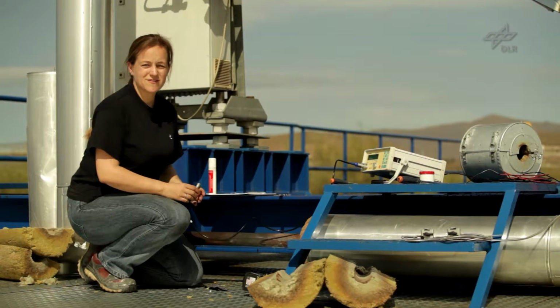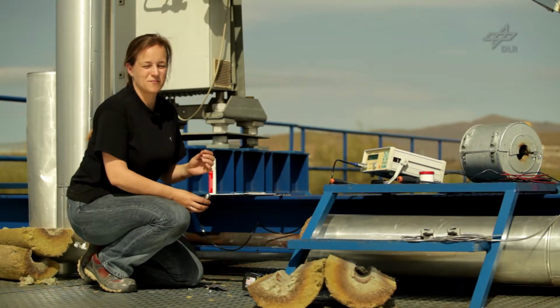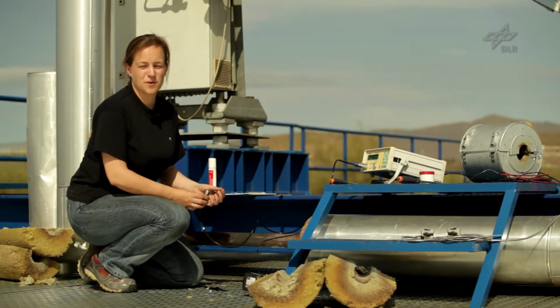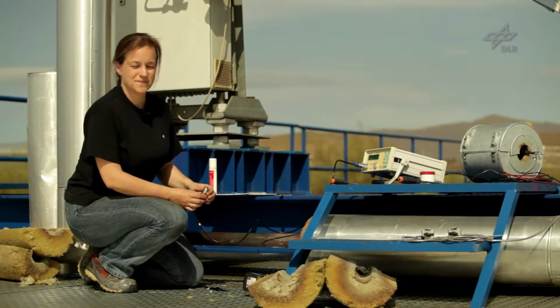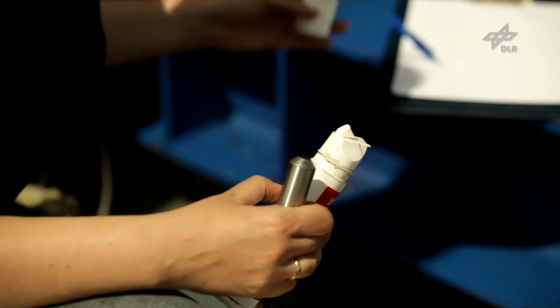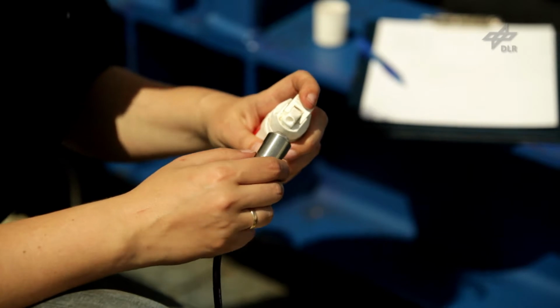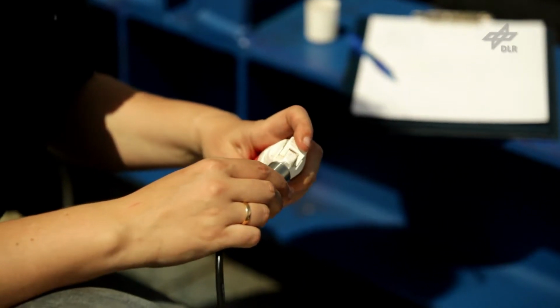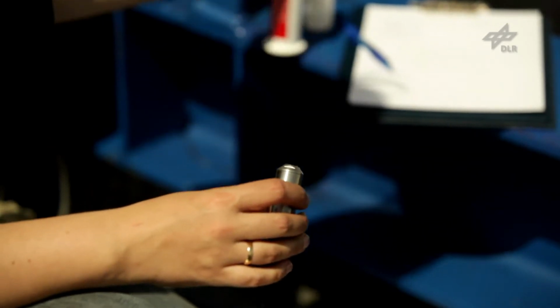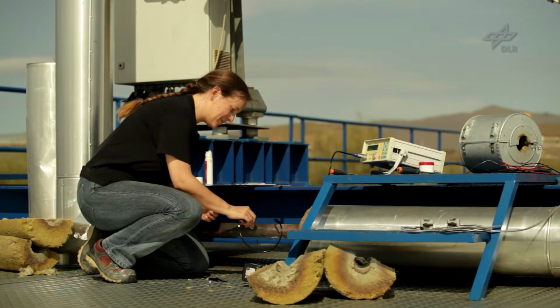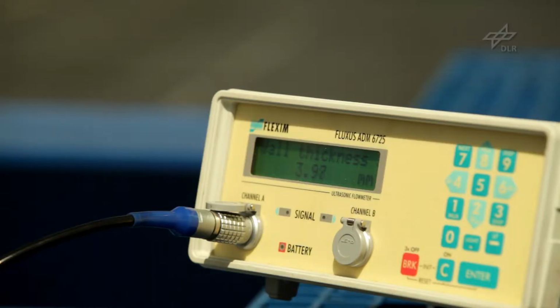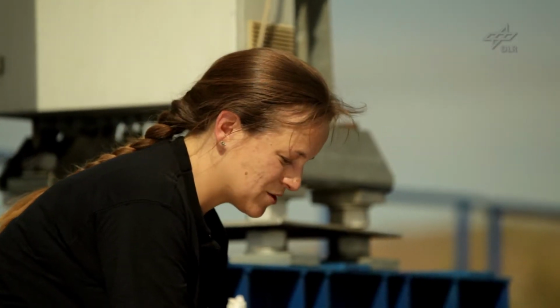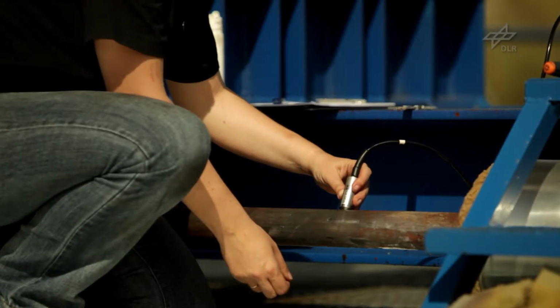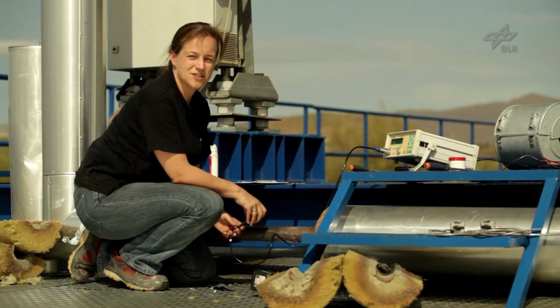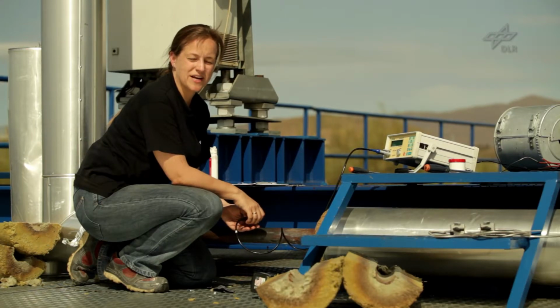The wall thickness of the pipe is determined by ultrasonic measurements. They use the travel time difference to determine the thickness from the time needed for the signal to pass through the wall material and its longitudinal speed of sound. We apply coupling gel to the tip of the sensor in order to assure that the acoustic signal passes well from the sensor to the pipe. And then we probe the pipe with the tip of the sensor. Again, we take several measurements around the circumference of the pipe and then calculate its average value. For the quality of those measurements, it is essential that the longitudinal speed of sound is entered correctly into the calculation.